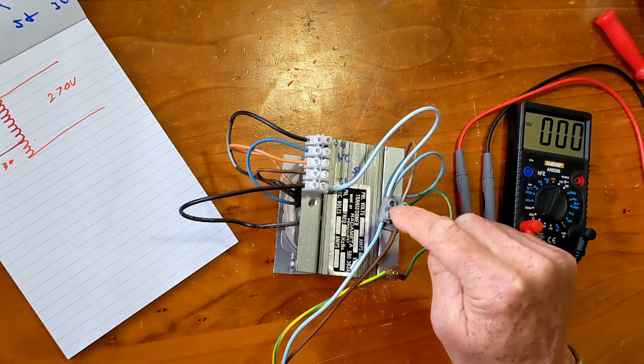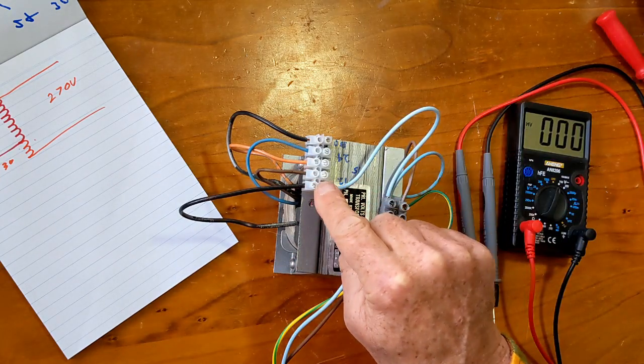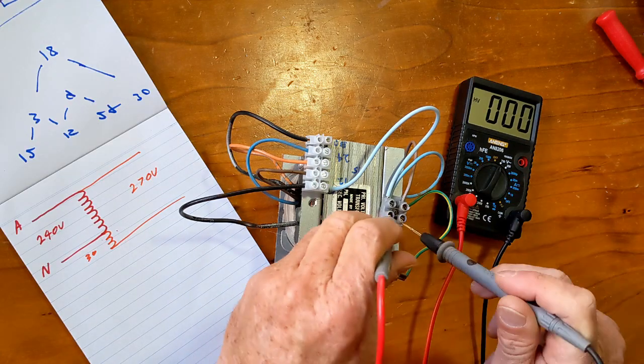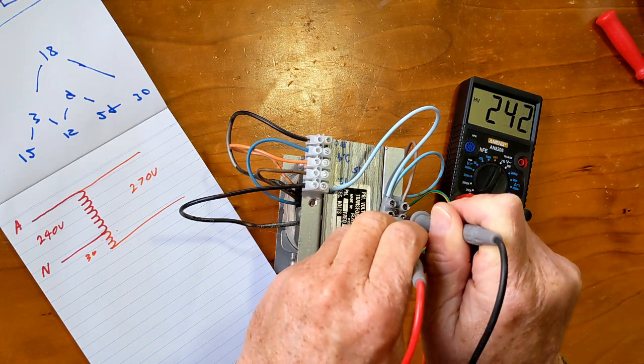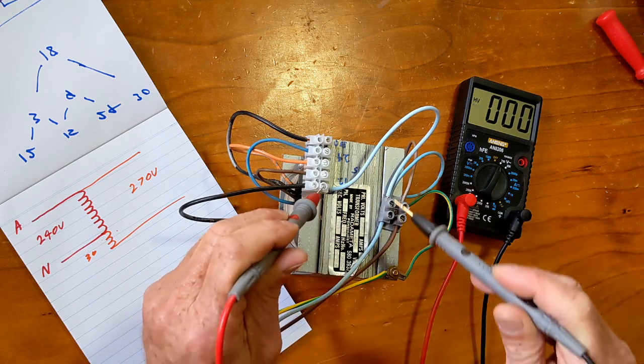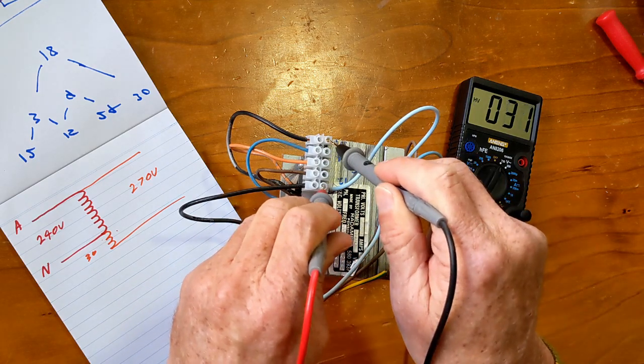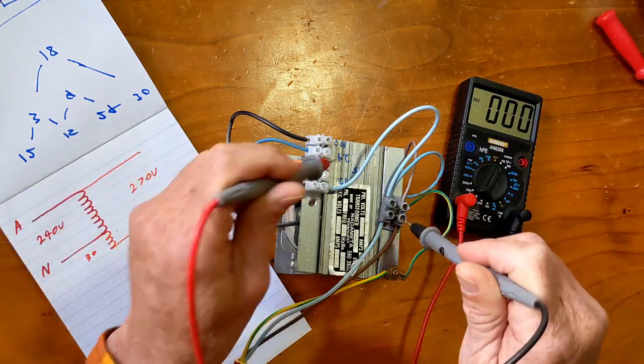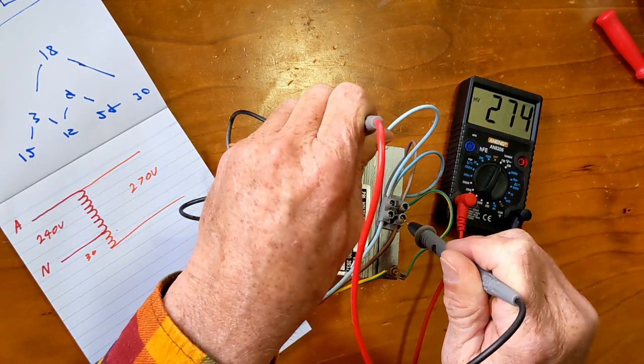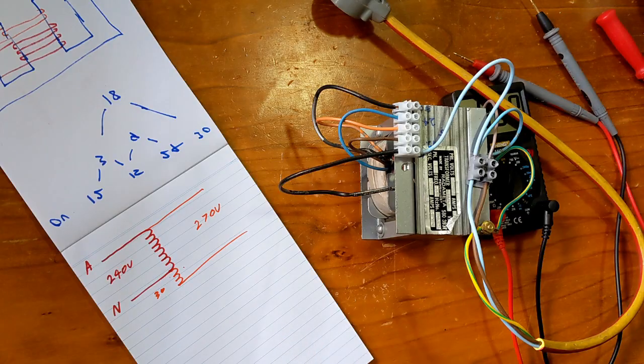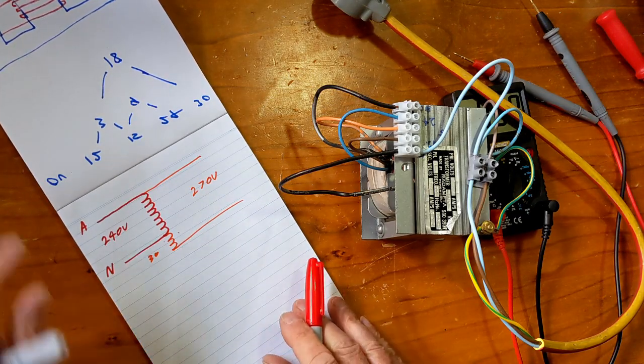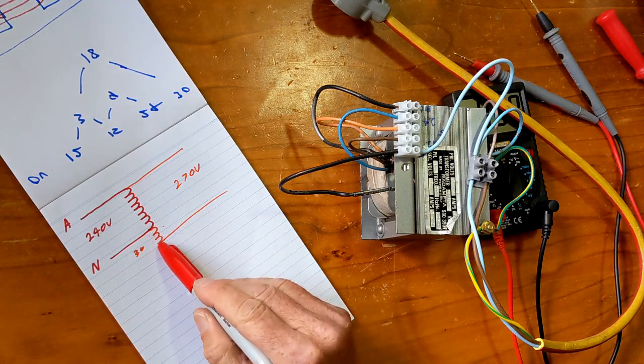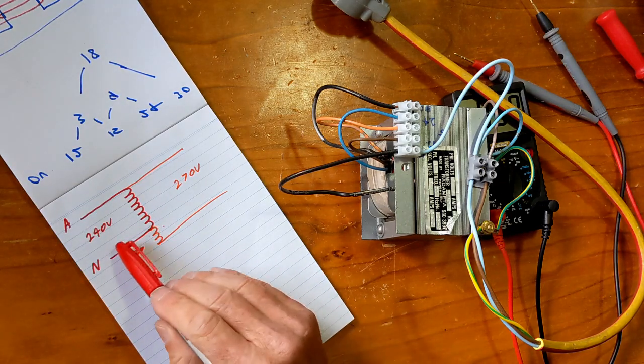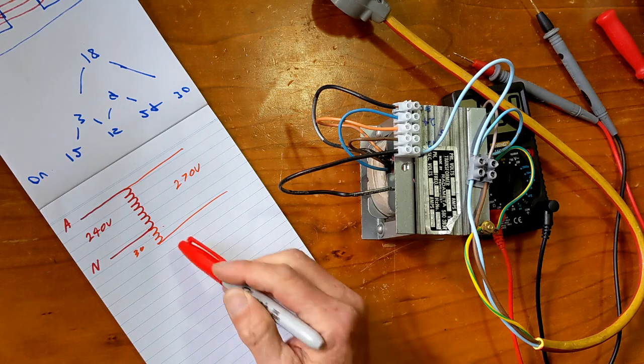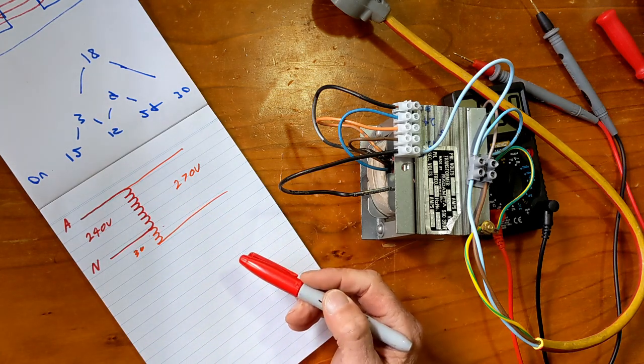Now I've connected the primary winding to the secondary winding. On the primary side, we have 240 volts. On the secondary side, we have 30 volts. If I add the primary to the secondary, I end up with 270 volts. Now doing this, you need to be a little bit careful, because if I connect this one backwards, the 30 volts will subtract from the 240 and I'll end up with a lower voltage out.